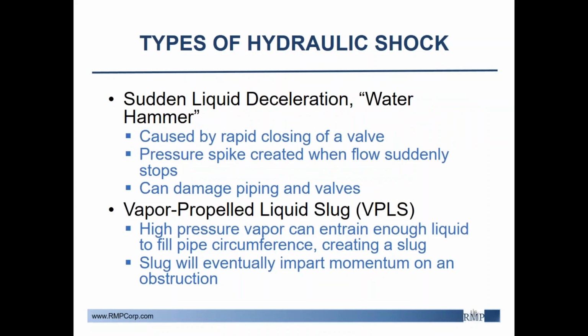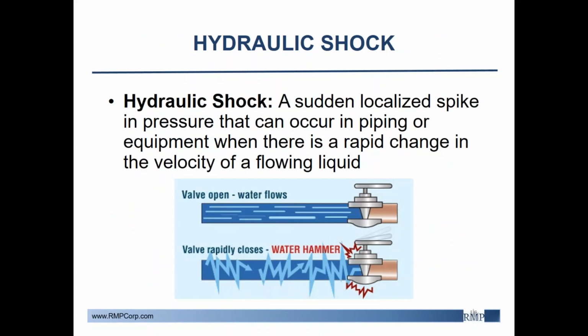There are 3 types of hydraulic shock. Sudden liquid deceleration, also known as water hammer, is caused by the rapid closing of a valve. This causes a sudden pressure spike when the velocity stops so quickly and the liquid essentially slams into the valve, as you can see actually from this picture on the previous slide.